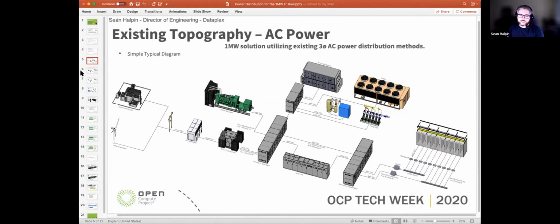Some of the main components are your medium voltage switchgear, your transformer bringing it down to whatever voltage you're looking for, your 400 volt three-phase, into your primary switchgear. Your primary switchgear then separates off to your air handling or mechanical loads and into your UPS or other supporting equipment, then on into your secondary switchgear, which subdivides out into your IT load.